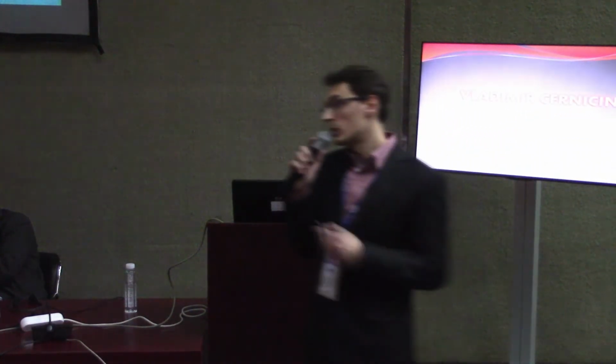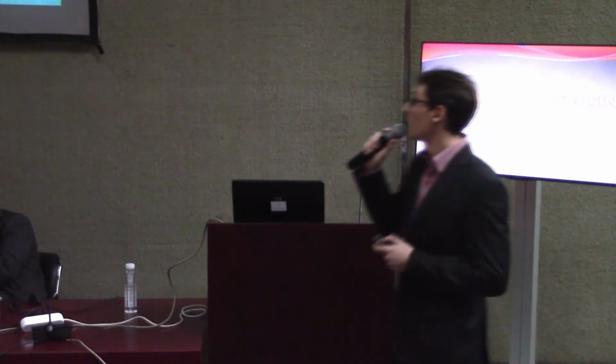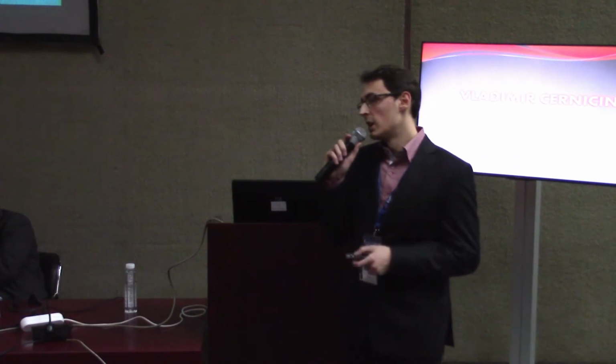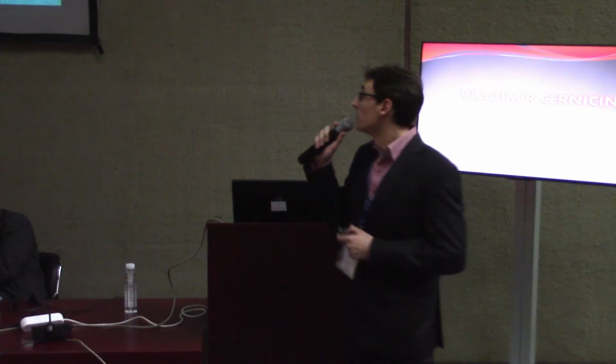As a conclusion, we look at 3 points. Global warming: from the point of view of global warming, CO2 is a good substitution for 404A. Also, combined with 134A, it's a good substitution because this is a medium GWP. Second, our goal was indirect impact on the environment through electric energy consumption. So, cascade is a good substitution, but transcritical two-stage CO2 is not.